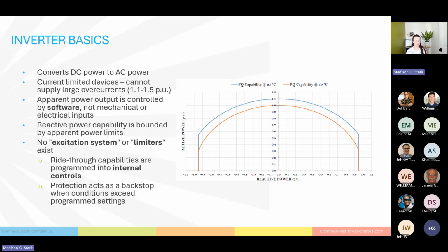So inverters are what's considered current limited devices. They have a defined amount of current that they can output, generally rated somewhere between 1.1 and 1.5 per unit of their nameplate rated capacity.